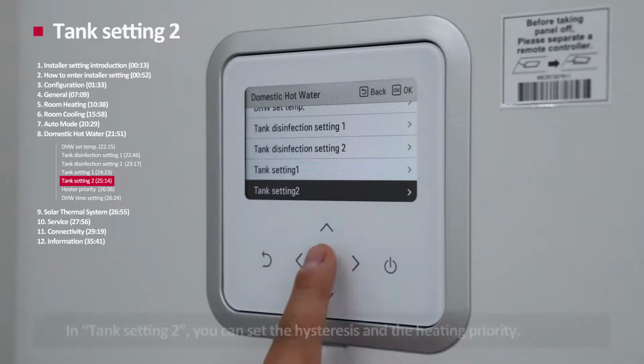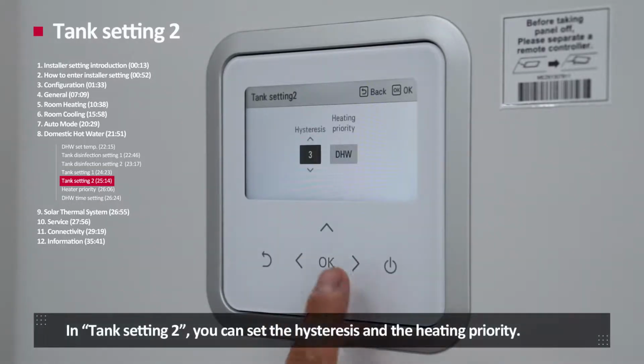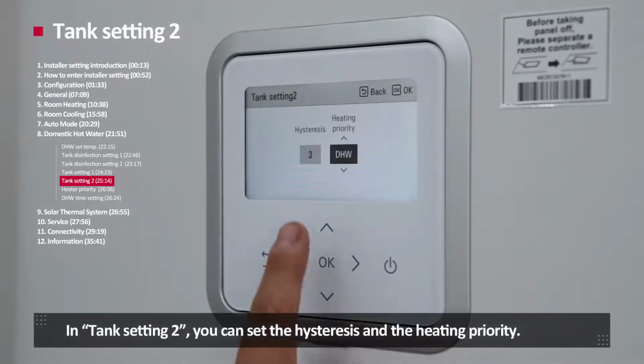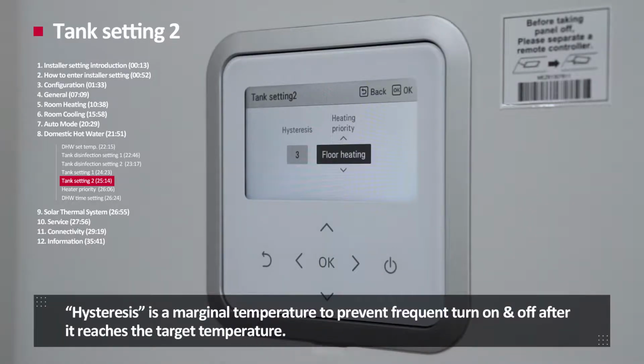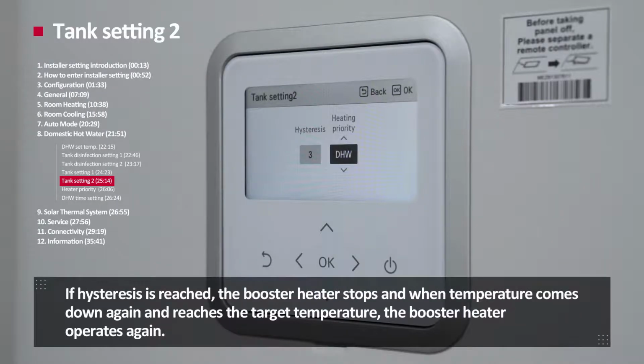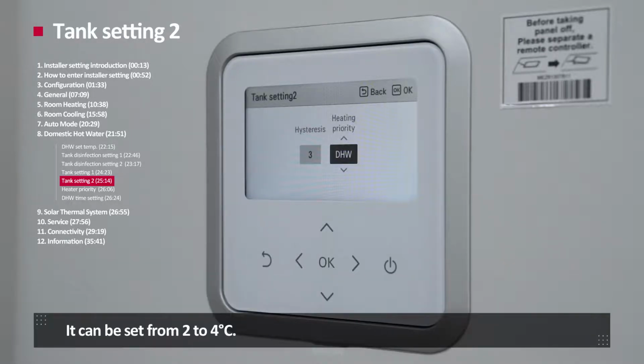Tank setting 2. In tank setting 2, you can set the hysteresis and the heating priority. Heat statuses is a marginal temperature to prevent frequent turn on and off after it reaches the target temperature. If hysteresis is reached, the booster heater stops, and when temperature comes down again and reaches the target temperature, the booster heater operates again. It can be from 2 to 4 degrees Celsius.